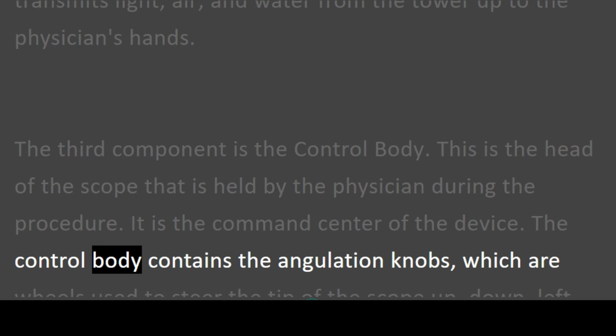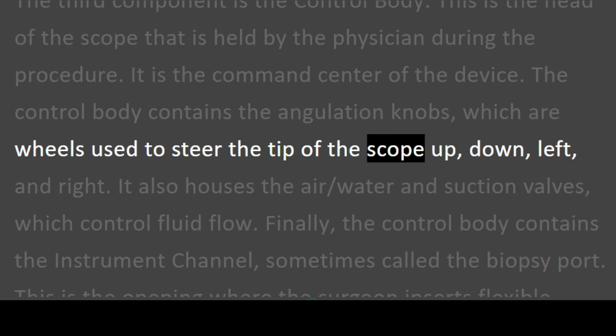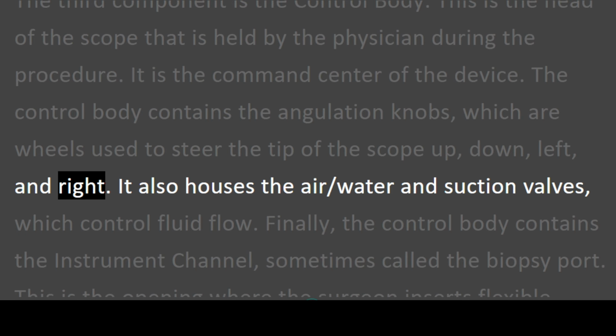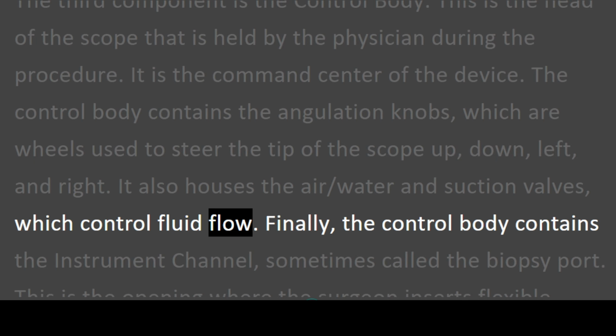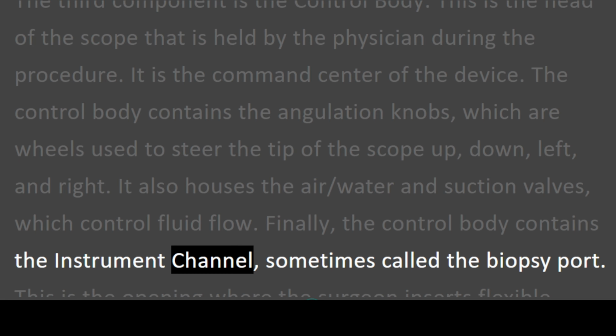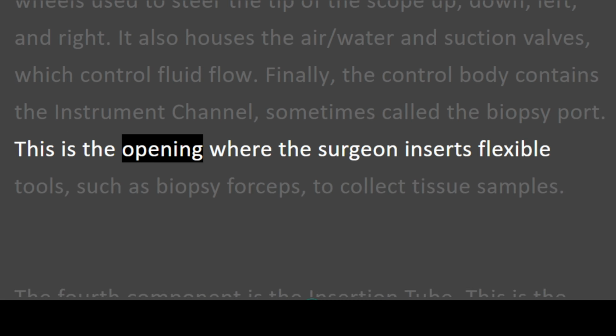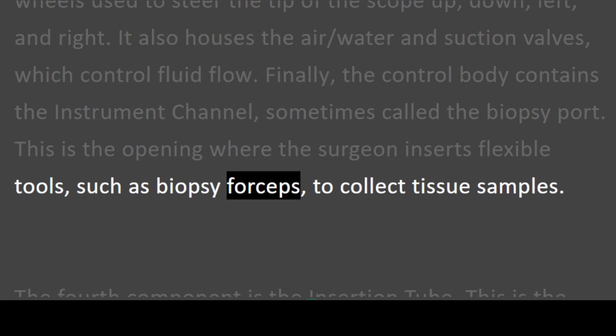The control body contains the angulation knobs, which are wheels used to steer the tip of the scope up, down, left, and right. It also houses the air/water and suction valves, which control fluid flow. Finally, the control body contains the instrument channel, sometimes called the biopsy port. This is the opening where the surgeon inserts flexible tools, such as biopsy forceps, to collect tissue samples.